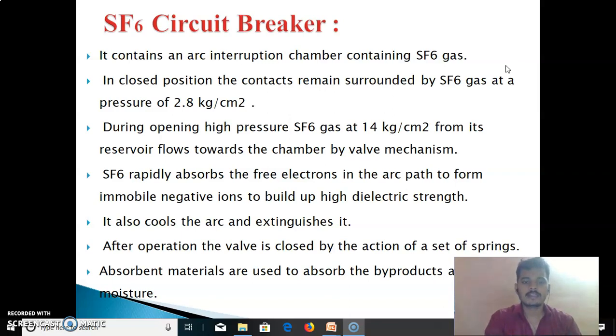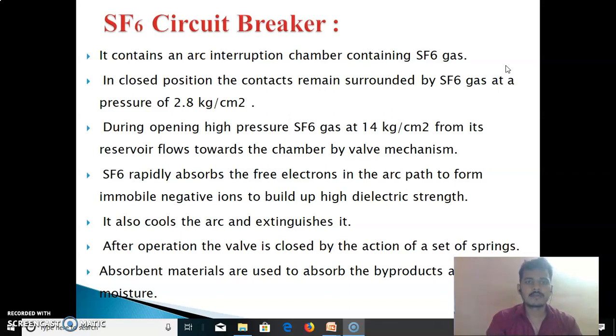The advantages of the SF6 circuit breaker: First, very short arcing period due to the superior arc quenching property of SF6. Second, it can interrupt much larger currents compared to other breakers. Third, there is no risk of fire, and it has low maintenance and light foundation. Fourth, there is no overvoltage problem and there are no carbon deposits.